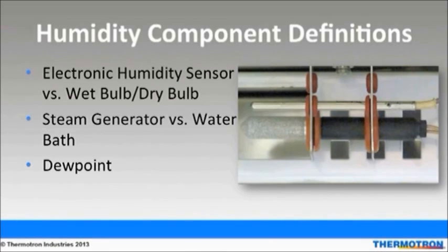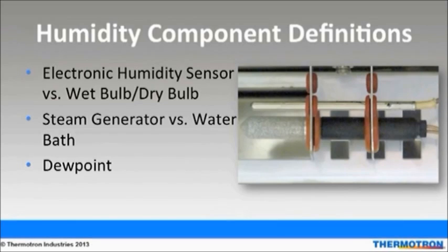A wet bulb-dry bulb system can require frequent replacement of wick socks, and the dirty water from the test can clog the humidity system. The steam generator produces high volumes of moisture and water vapor consistency, which is good for transitions. The water bath system can't generate high volumes of moisture and has poor low humidity control due to the water in the bath; however, it is good for steady state testing. The dew point is the temperature to which air must be cooled for it to reach saturation.